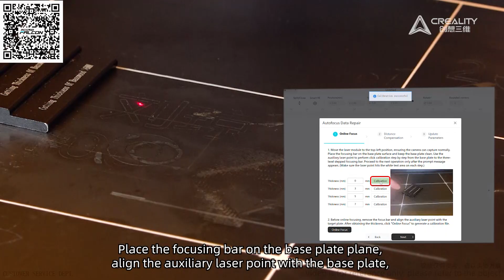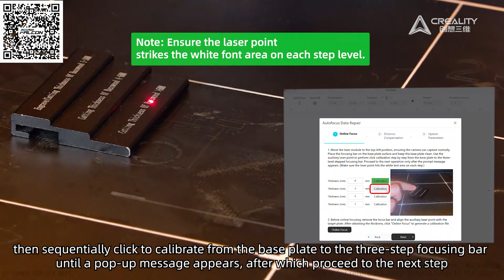Place the focusing bar on the baseplate plane. Align the auxiliary laser point with the baseplate. Then sequentially click to calibrate from the baseplate to the 3-step focusing bar until a pop-up message appears, after which proceed to the next step.